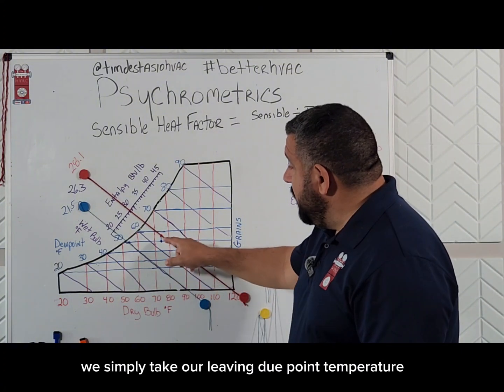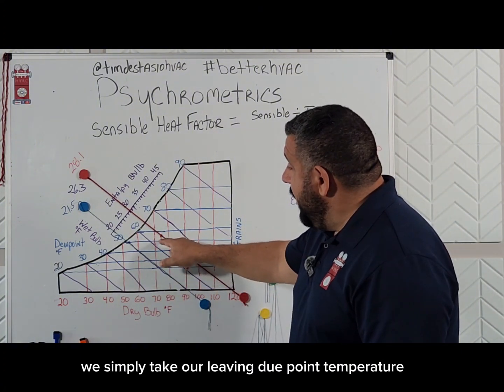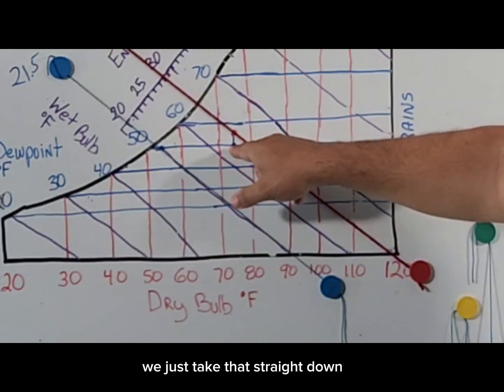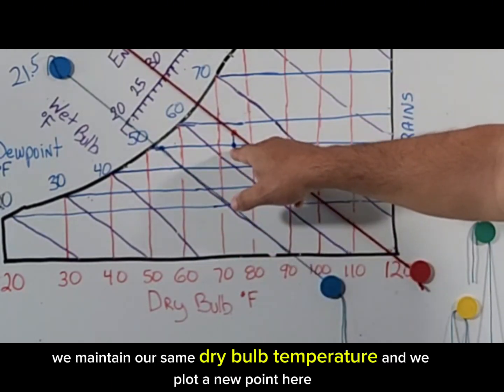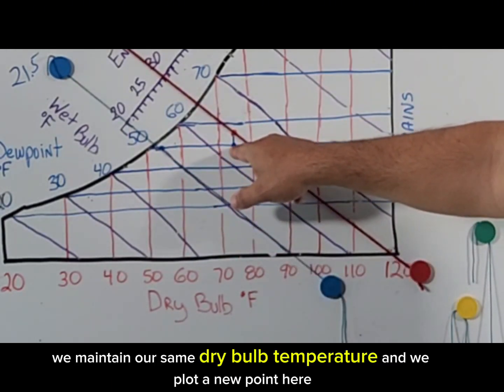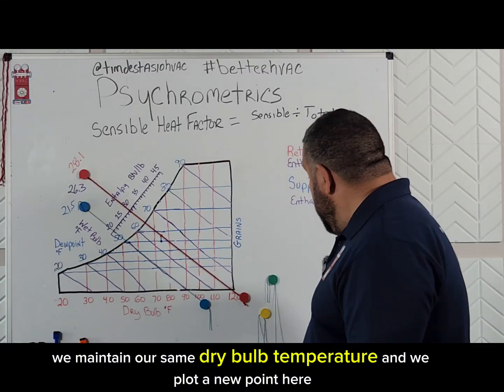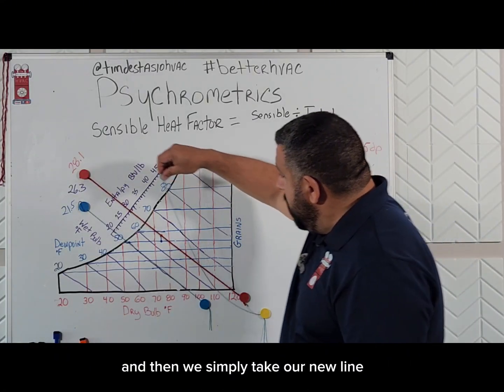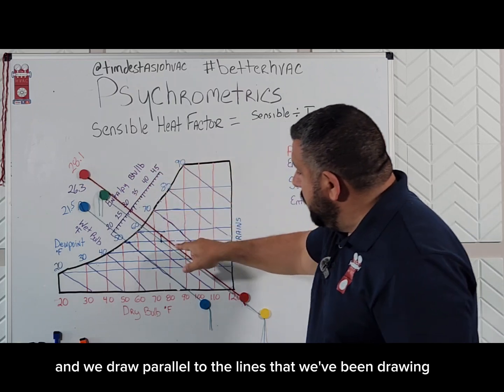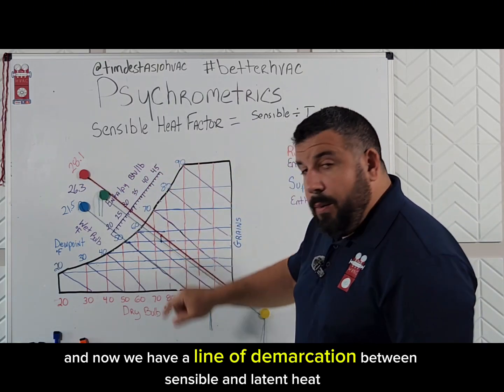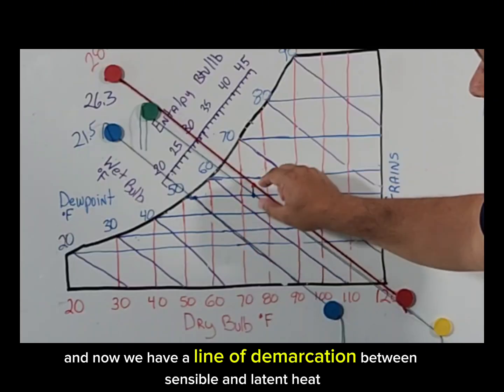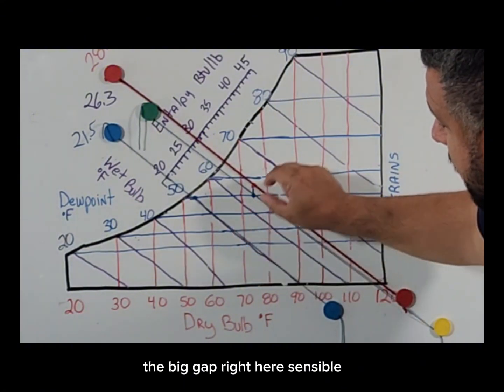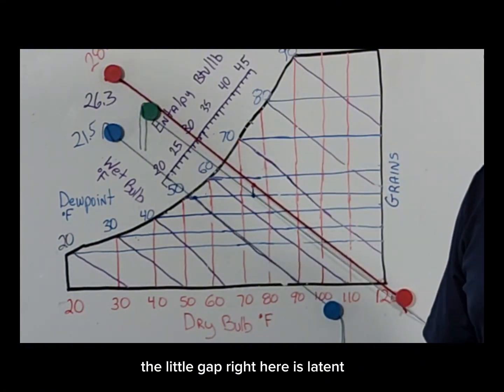Last time we talked about that — we simply take our leaving dew point temperature, which in this case was 50. We just take that straight down, we maintain our same dry bulb temperature, and we plot a new point here. Then we simply take our new line and draw it parallel to the lines that we've been drawing. Now we have a line of demarcation between sensible and latent heat. The big gap right here is sensible; the little gap right here is latent.